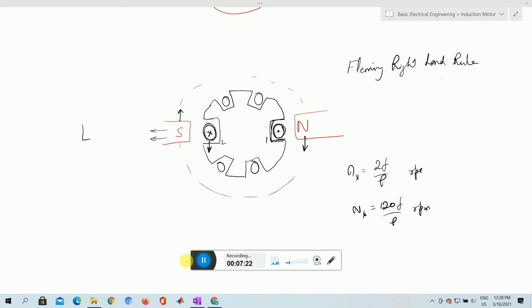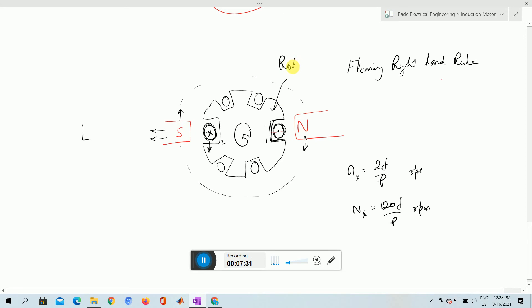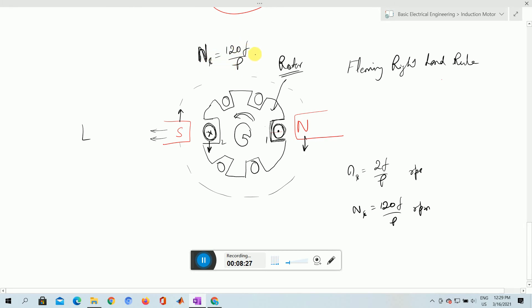From this, what we understand is that this arrangement is called the rotor of the induction motor. The rotor is not mechanically in contact with the stator — there is an air gap between the rotor and the stator. We are assuming there is a virtual north pole on the upper side of the stator, because when three-phase supply is given to the stator, it creates virtual north and south poles that rotate clockwise. If we assume we are sitting on the north pole, we feel the conductor rotating anticlockwise — at the synchronous speed ns = 120f/p RPM.